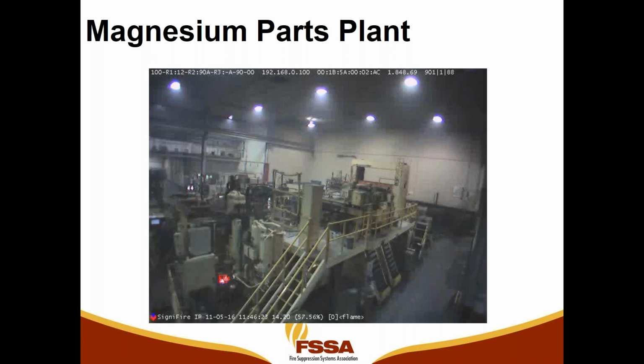We add a masking zone over that flame and set the system up so that if it sees a flame in the mask zone, it doesn't go into alarm. But if the flame grows and breaks outside of the masking zone, the system goes into alarm because it's been tracking it. Now, nights and weekends, there's a schedule so that all the blocking zones can go away. So it's alarming for flame in the entire field of view. Smoke detection can be enabled on nights and weekends, and then a motion detection zone can be enabled as well for security.